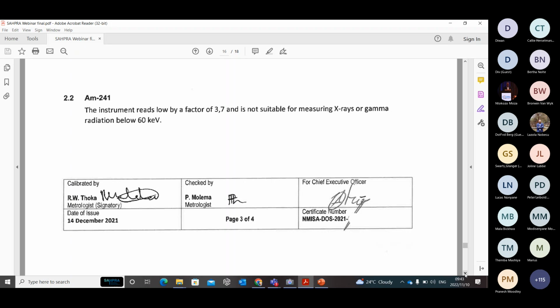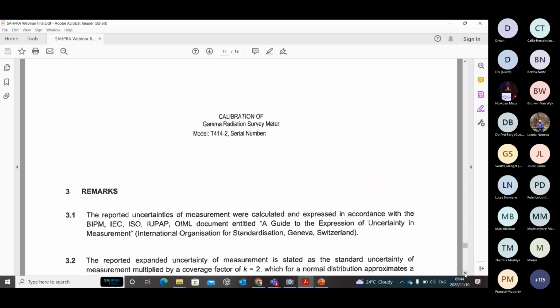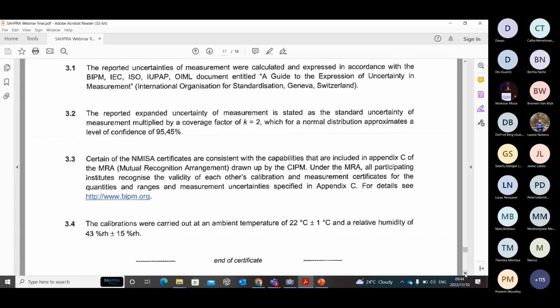Because sometimes there are instruments that need to be calibrated in X-rays, and you find that there are no facilities to calibrate in X-rays. So the americium will also just help you to give an indication that the instrument you use can be used for X-rays and also for gamma rays of energies below 60 keV. And then, as you see there at the bottom, there are signatures of the people who have done the measurements. As I mentioned, it's a legal document, so there should be some form of traceability to the individuals who have performed the calibration.